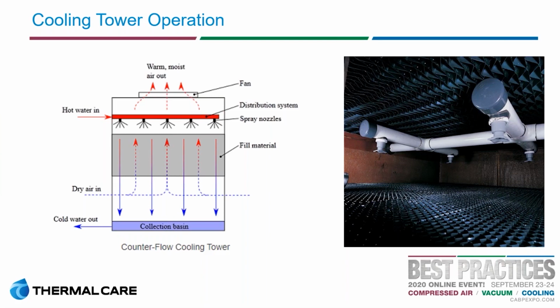And those gray nozzles sticking down there actually use centrifugal force. As that water is pumped through them, it spins out and sprays over. And that black structure there that looks kind of like a honeycomb is what's known as fill. That fill creates a lot of surface area because we want to maximize our ability to evaporate, because that maximizes the capacity of the cooling tower. So by having that honeycomb structure in there, we guarantee the maximum amount of surface area available.